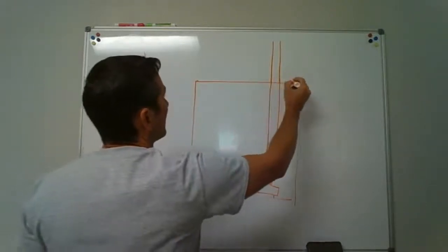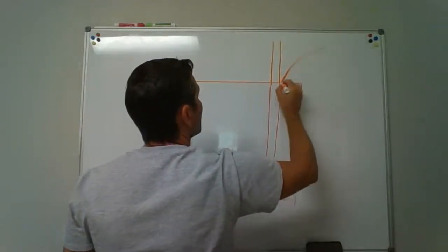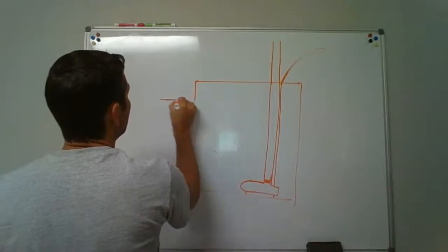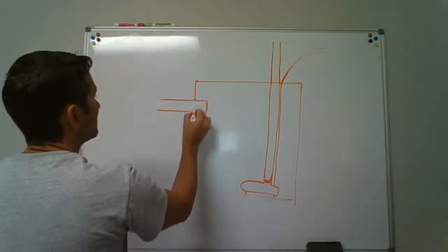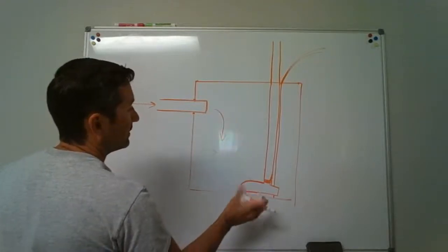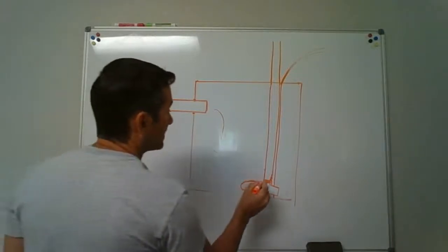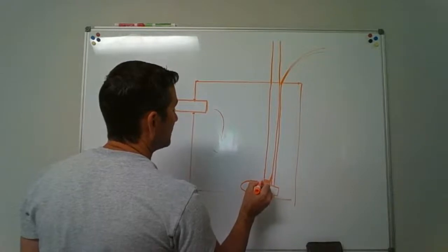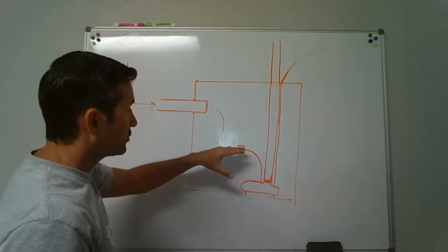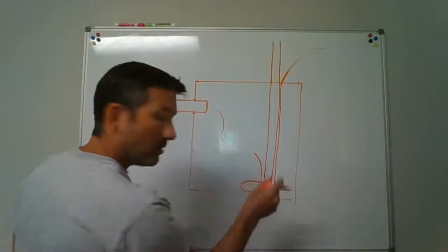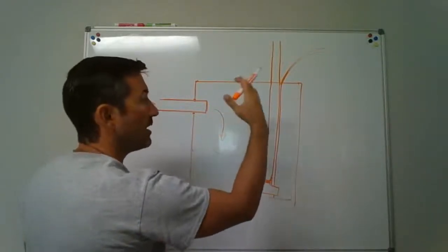The pump sits on the bottom. It also has a place where the wire comes through. Okay, that's wired down here to the pump. On the side, where another gasket comes through, is going to be the inlet for the drain. That gets sealed with a gasket. So everything is draining this way into here and just dumps down into the tank. And then it says this pump has a float switch. Now you're going to strap this. It's got a cord to it, and most of them have a float switch. When the float switch is down, hanging down, it doesn't kick on until that float switch comes up high enough.